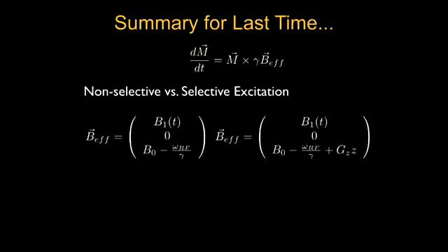In this situation, we assume on resonance, meaning the carrier frequency, omega RF, is the same as your main magnetic field frequency. So it will be canceled out to 0, and everything else is left over as the envelope function. If there's a gradient, then on resonance, the only component left is the frequency controlled by the gradient. So at different locations, there will be a different frequency component, and by that, you can have a selective excitation.